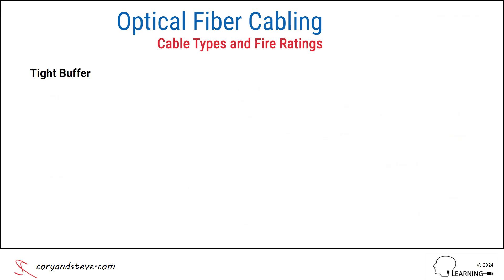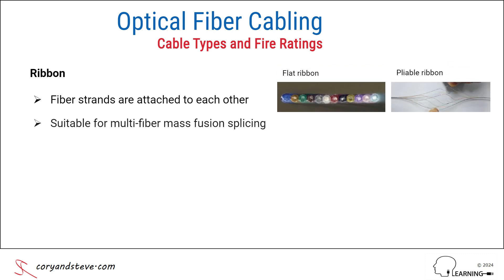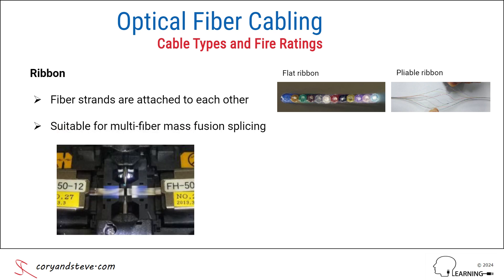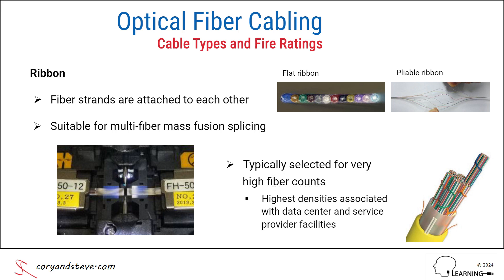The third type of cable construction is ribbon, where the fiber strands are attached to each other in a row, creating a flat or pliable strip of fibers suitable for multi-fiber mass fusion splicing, as shown here. The ribbon construction is typically selected for very high fiber counts, all the way up to nearly 7,000 strands in a single cable. Note that the highest densities numbering in the thousands are typically associated with data center and service provider facilities.